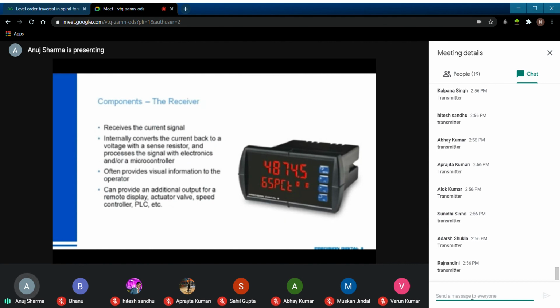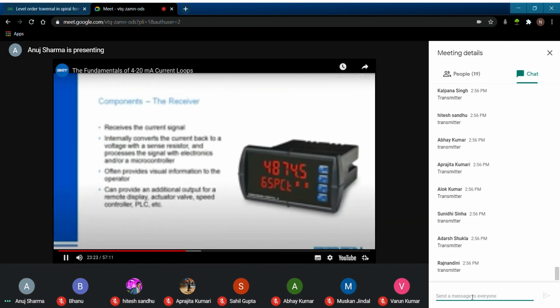Then you've got the receiver or receivers. The job of these is to receive that current signal. These are your panel meters, your chart recorders, the inputs into a PLC, the input cards on a SCADA system, essentially anything else that is reading that current loop.